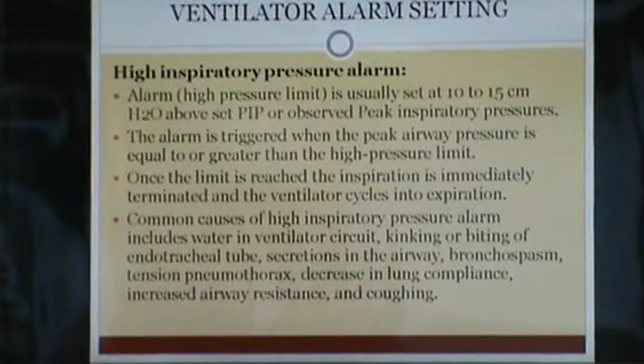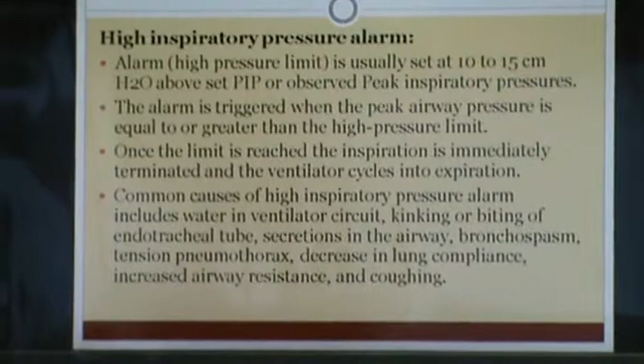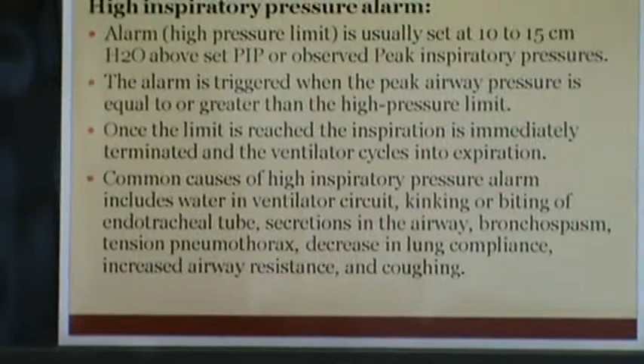Ventilator alarm settings: the high inspiratory pressure alarm. The alarm is set 10 to 15 centimeters above whatever desired PIP you have set. This will be triggered when the actual PIP crosses the set alarm, and that will be the indication to look for any water in the circuit, kinking or biting of the endotracheal tube, secretions in the airway, bronchospasm, tension pneumothorax, decreased lung compliance. We have to look for these if there is a high inspiratory pressure alarm. That is a very important alarm in that sense.